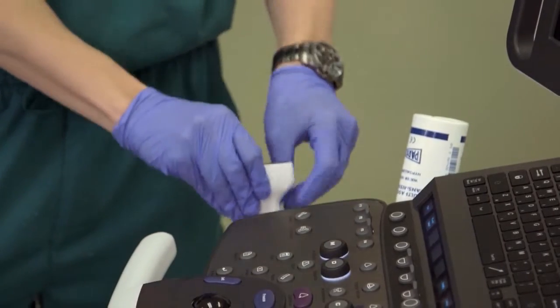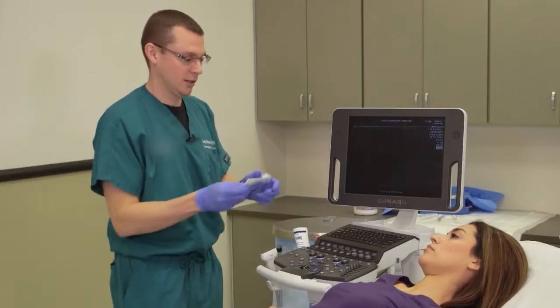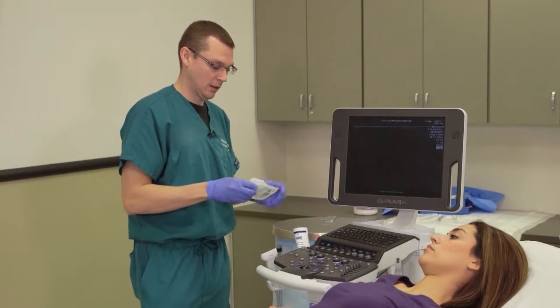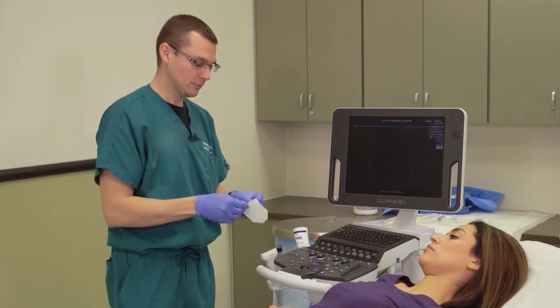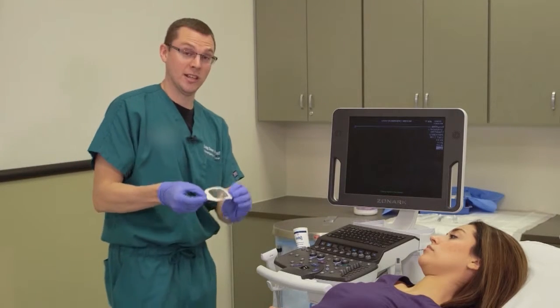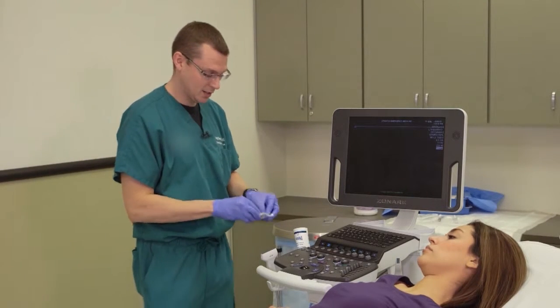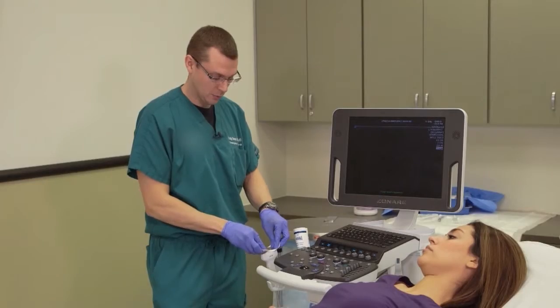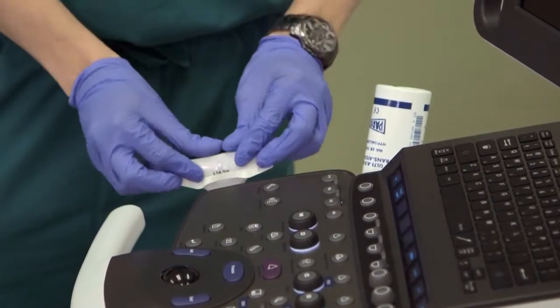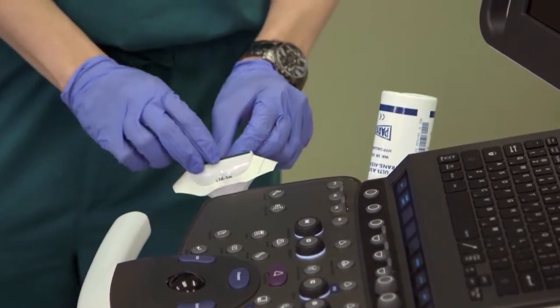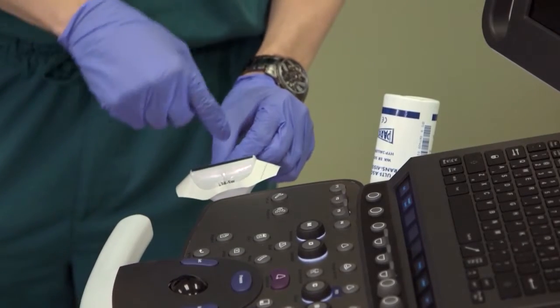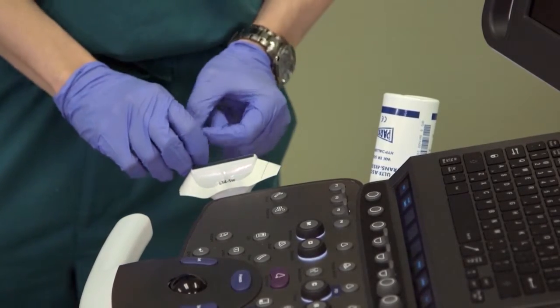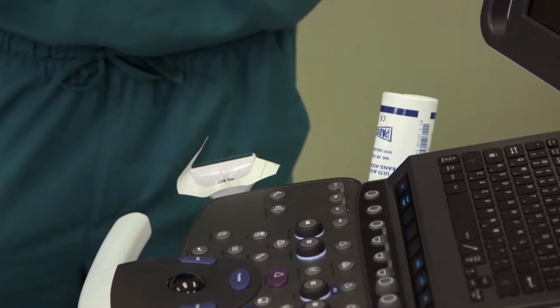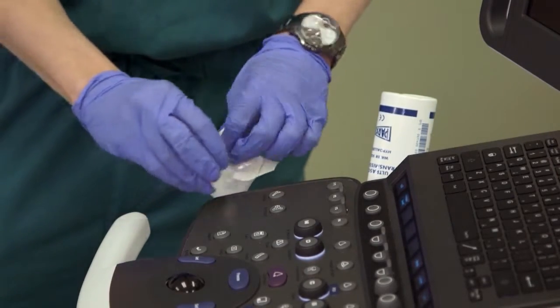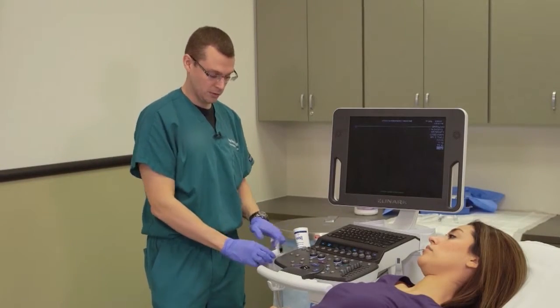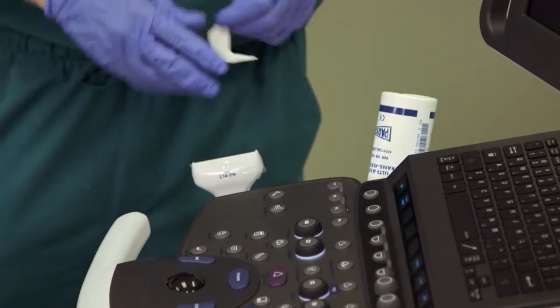So the first thing I'm going to do to prepare the transducer is take the Tegaderm out of its package, and it has one side that's adhesive. I'll take that adhesive portion and pull it really taut. I'll put it right over the surface of the transducer and then run my finger across it to get out any air bubbles. As long as there are no air bubbles between the Tegaderm and the footprint of the transducer, you'll be able to image straight through it. So you want to get all the air bubbles out. And then you just peel off and adhere it right to the tip of the transducer.